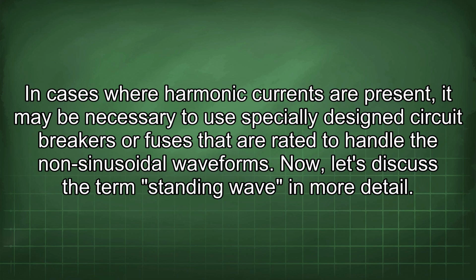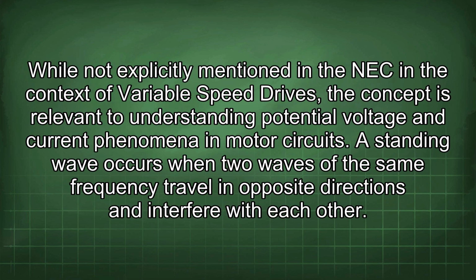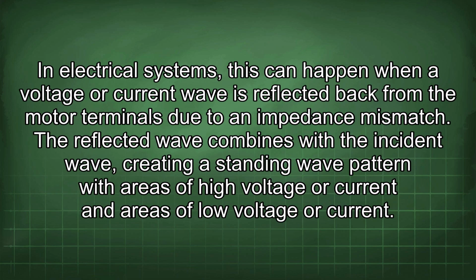Now, let's discuss the term standing wave in more detail. While not explicitly mentioned in the NEC in the context of variable speed drives, the concept is relevant to understanding potential voltage and current phenomena in motor circuits. A standing wave occurs when two waves of the same frequency travel in opposite directions and interfere with each other. In electrical systems, this can happen when a voltage or current wave is reflected back from the motor terminals due to an impedance mismatch. The reflected wave combines with the incident wave, creating a standing wave pattern with areas of high voltage or current and areas of low voltage or current.